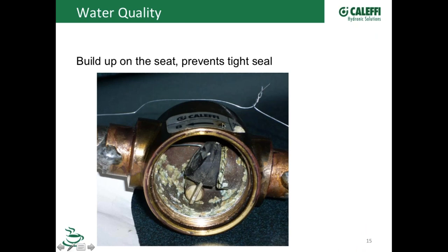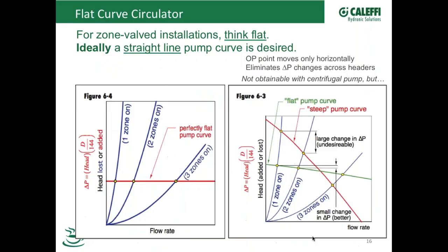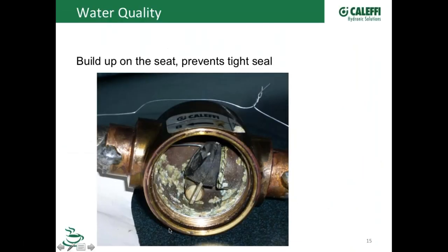And also notice, you can't quite see it on the tags, I think all of our zone valves, the Z1s, do have that CV number on the tag on one side or the other. So if you have one where the box is missing or something like that and say, well, what valve do I have? Well, number one, you can look in the end like the picture I just showed you and see the port size going through it, but it should have a sticker on it telling you the CV of that valve. On the opposite side of that valve body too, Bob, there's actually going to be a stamped model number. So it'll be a Z2, you know, whatever.